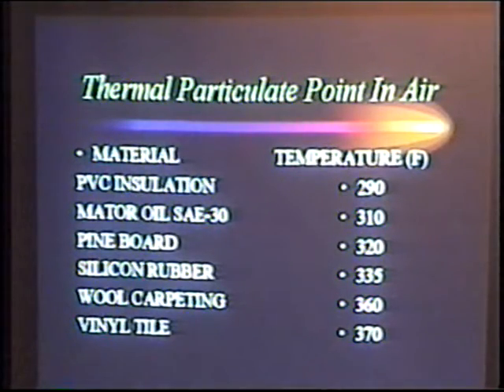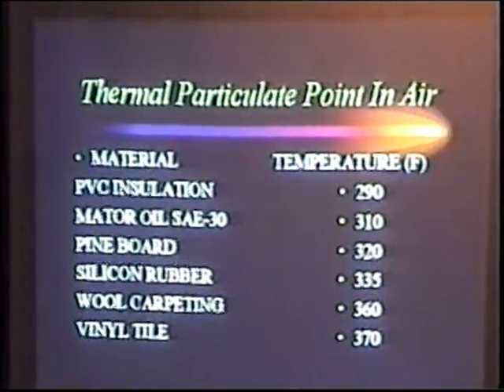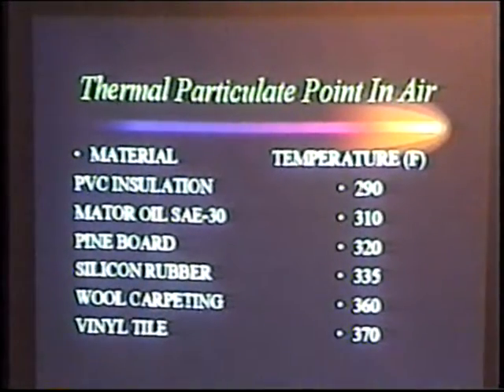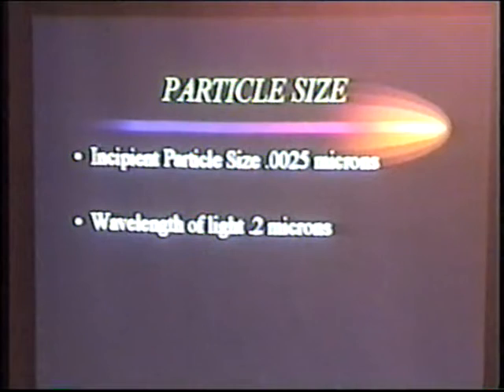Let's talk a little bit about these invisible particles, which we also term particulates. This is some common material up here, PVC insulation, and the associated temperature where it starts to produce these invisible particles. As you can see, PVC insulation is about 290 degrees. Motor oil is 310, pine board 320, and so forth. Keep in mind, at this incipient stage, we're not producing smoke, there's no flame, there's nothing yet. It's just these invisible particles being produced.